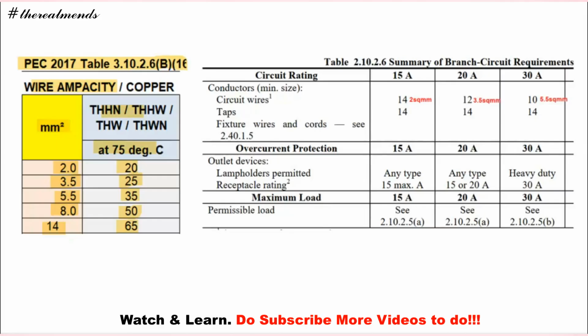And then may table tayo na yung 2.10.2.6 summary of branch circuit requirements. Pag yung overcurrent protection mo daw, yung circuit breaker is 15 amperes, so yung kanyang circuit wires is 2 square mm. Pag 20 ampere trip, so minimum is 3.5 square mm or number 12. Pag 30 ampere trip, so yung circuit wires mo is 5.5 square mm. So, ito yung gamitin natin. Itong table ng ampacity, also itong table ng branch circuit requirements.